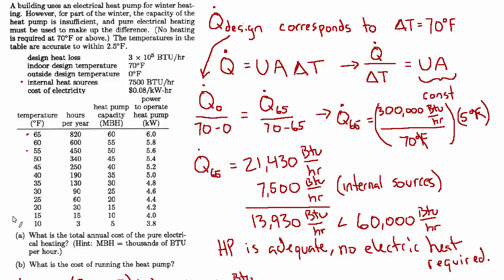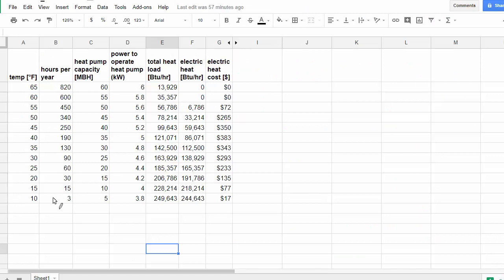And we want to know how much that costs. So let's turn that BTU per hour into kilowatts, since that's how we buy electricity. So we'll divide by 3412 BTU per hour per kW. That is 1.99 kW. And now to turn this into cost, we need to multiply by the number of hours and then the cost per kWh. So we're dealing with the T equals 55 condition, happening for 450 hours a year. So we'll multiply by 450 hours. And the average cost of electricity is 0.08 per kWh. And that equals about $72. So that is the cost associated with this row.